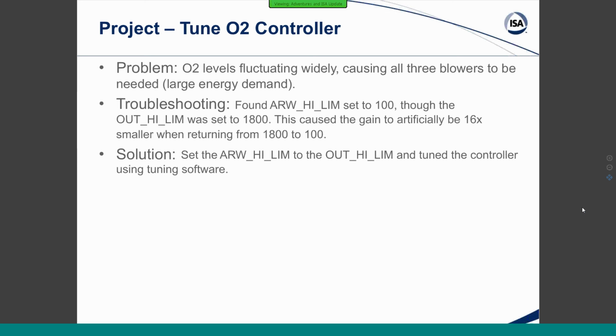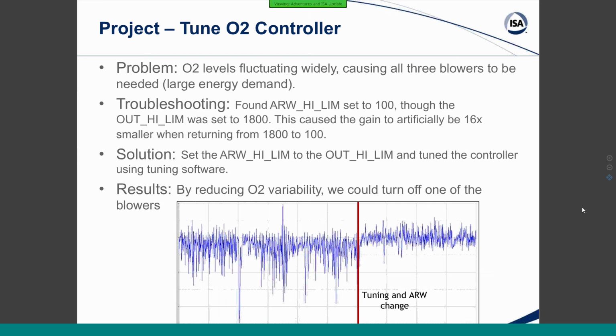So we set the ARW limit to the output high limit and then tuned the controller normally, which greatly reduced the variability in our oxygen level and allowed us to turn off one of the blowers completely for much of the year, saving quite a bit in energy costs.